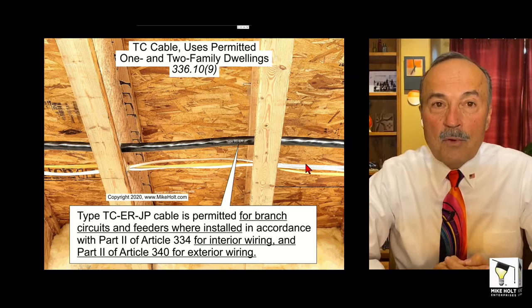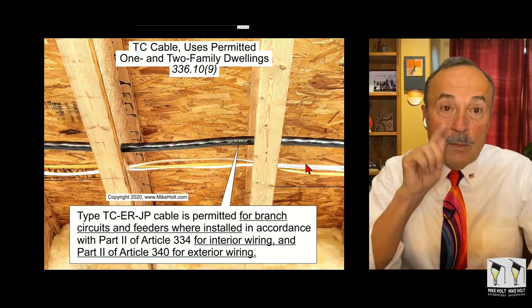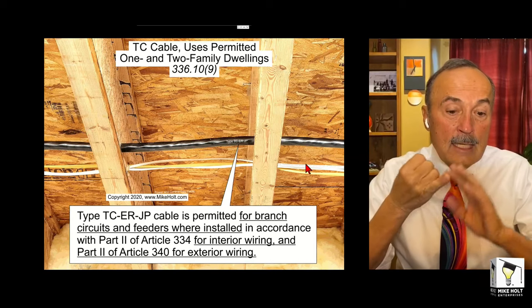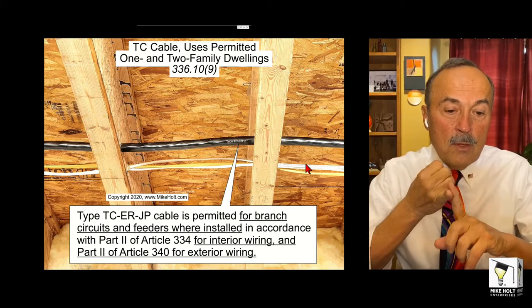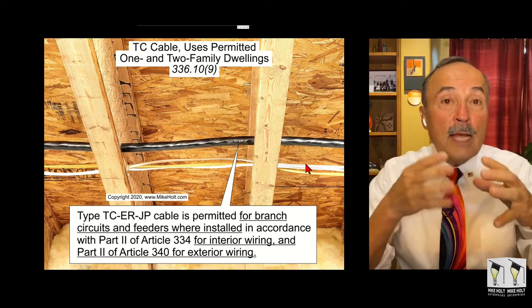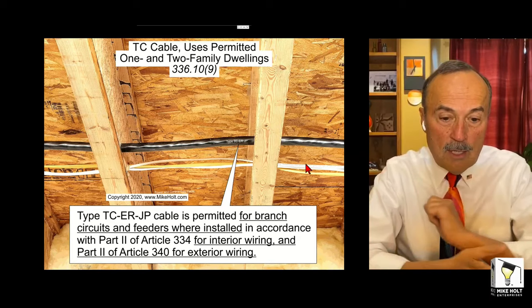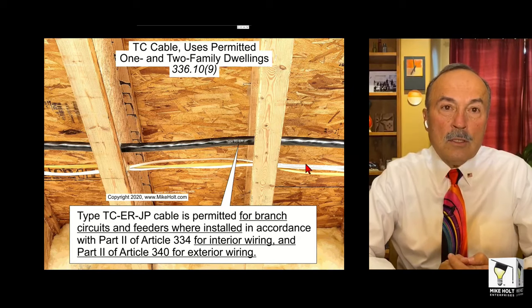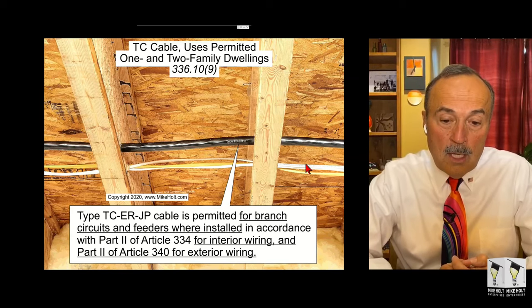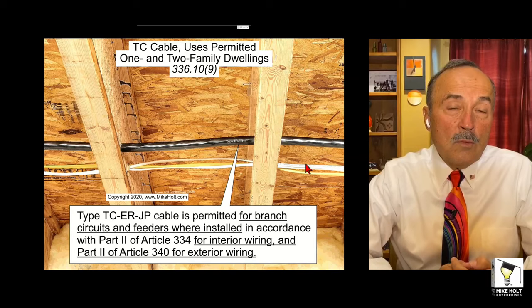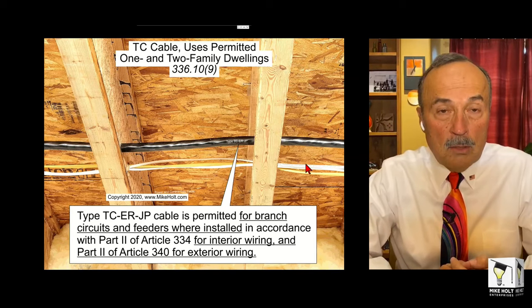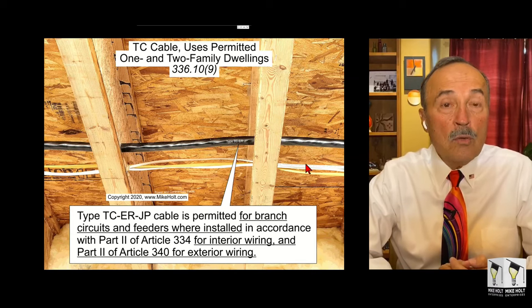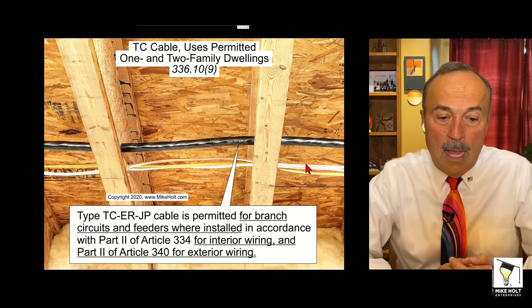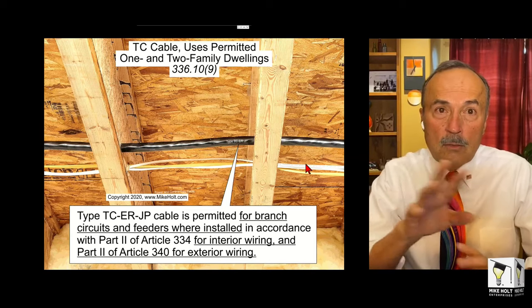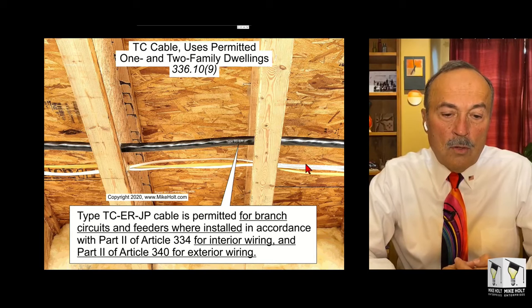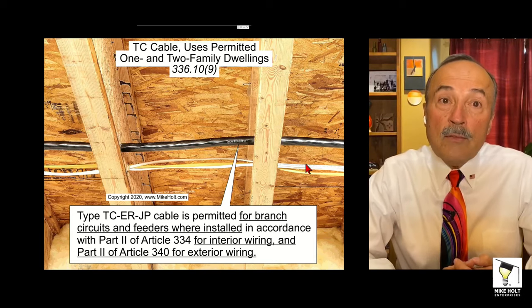So what happened was, in tray cable, they came up with these special configurations. But if you're going to use it in a dwelling unit, it has to be what? TC-ER-JP, that's tray cable, exposed runs, joist pull. And UL has a standard for these types of scenarios. It is permitted for branch circuits and feeders. So yes, you can use tray cable for branch circuits and feeders, if installed in accordance with Part II of 334, in other words, Romex. If you want to put this tray cable inside of a building, you can. And you wire it like it would have been what? Romex requirements. And that's Part II only, not Part III. So we're not going to get into that. And Part II of Article 340, exterior wiring. In other words, UF cable is Article 340.